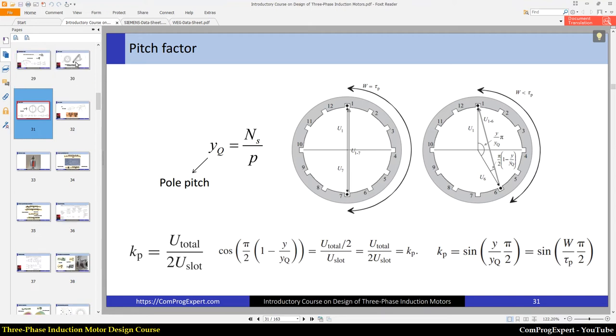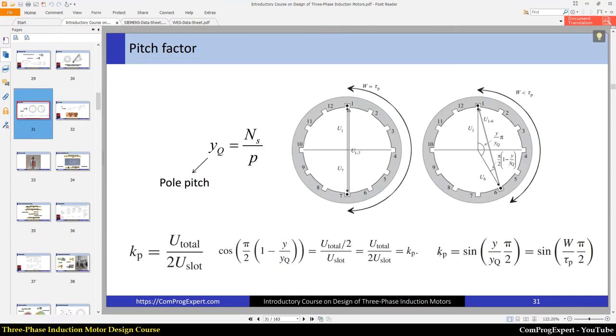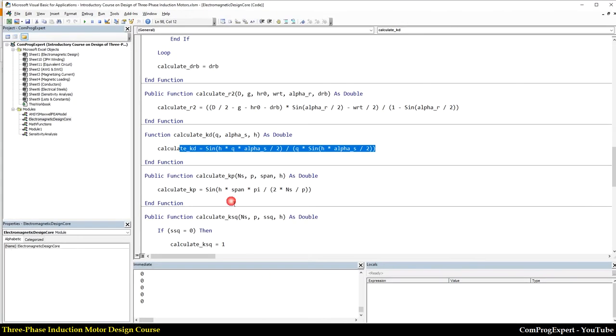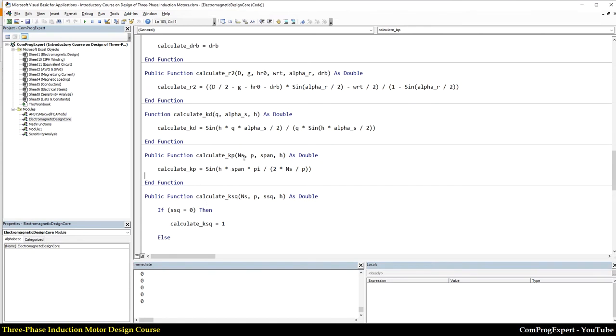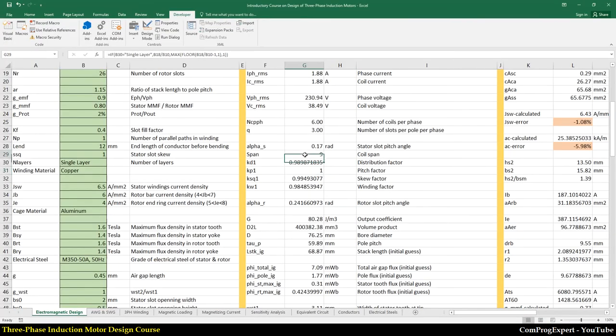Also, if you are interested, you can refer to the second chapter of this reference. And this is the equation of the pitch factor. I implemented this equation here, calculate KP, pitch factor. We have these inputs: number of stator slots, poles, span, and H, right? span is defined as number of stator slots between two coil arms of the winding, right? So number of stator slots between two coil arms.